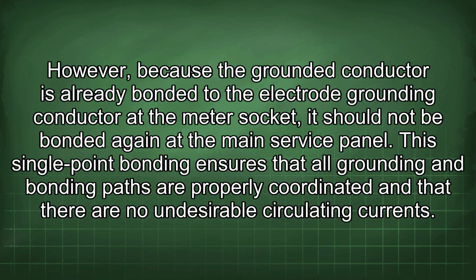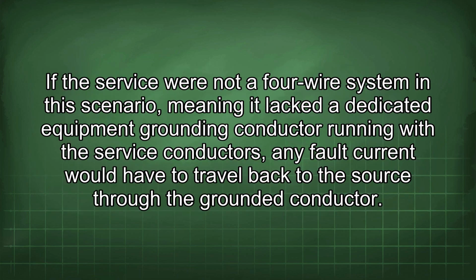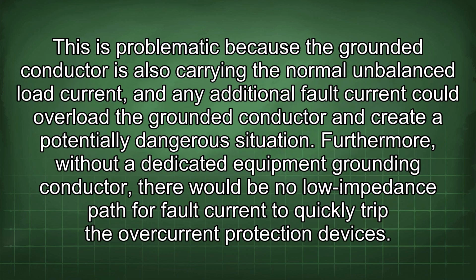However, because the grounded conductor is already bonded to the electrode grounding conductor at the meter socket, it should not be bonded again at the main service panel. This single-point bonding ensures that all grounding and bonding paths are properly coordinated and that there are no undesirable circulating currents. If the service were not a 4-wire system in this scenario, meaning it lacked a dedicated equipment grounding conductor running with the service conductors, any fault current would have to travel back to the source through the grounded conductor. This is problematic because the grounded conductor is also carrying the normal unbalanced load current, and any additional fault current could overload the grounded conductor and create a potentially dangerous situation.